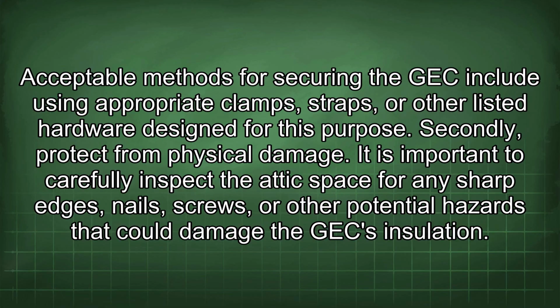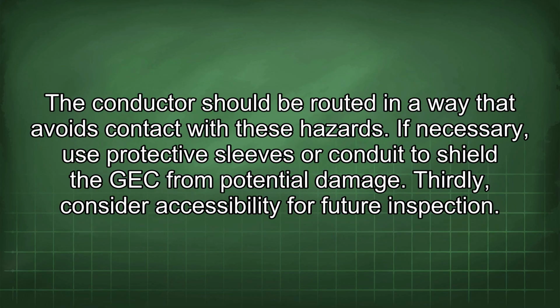Secondly, protect from physical damage. It is important to carefully inspect the attic space for any sharp edges, nails, screws, or other potential hazards that could damage the GEC insulation. The conductor should be routed in a way that avoids contact with these hazards. If necessary, use protective sleeves or conduit to shield the GEC from potential damage.